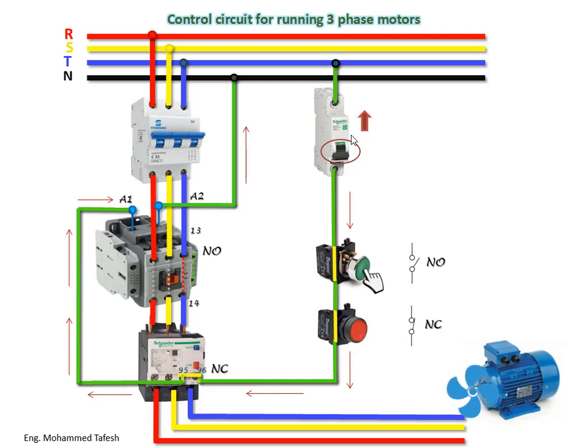The motor is now running. As soon as an electrical signal passes to the contactor coil, the three power poles of the contactor close, connecting the power circuit to the motor. With an electric voltage applied to the motor, current passes from the network R, S, T through the main circuit breaker, through the contactor, then through the overload, and finally to the motor to operate. In this way, you control the motor by controlling the contactor itself by sending an electric signal to the contactor coil.